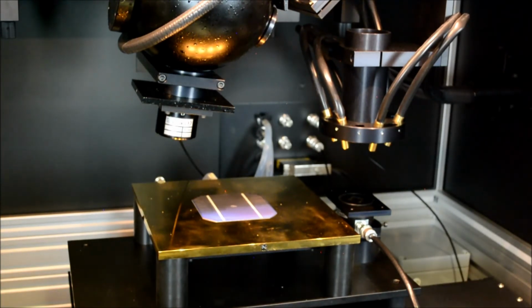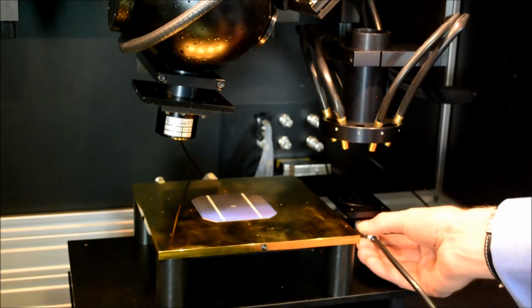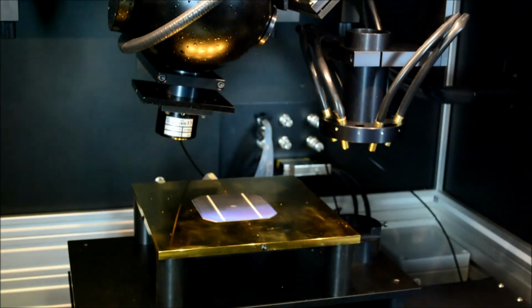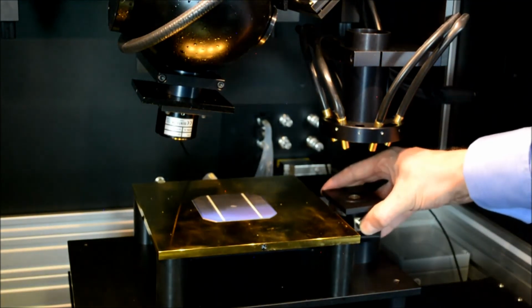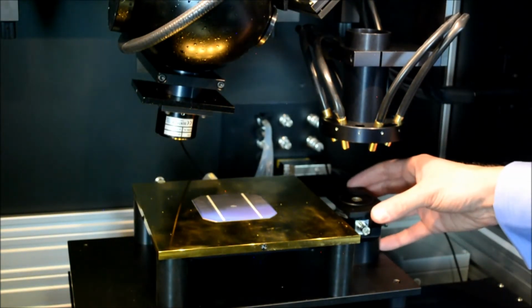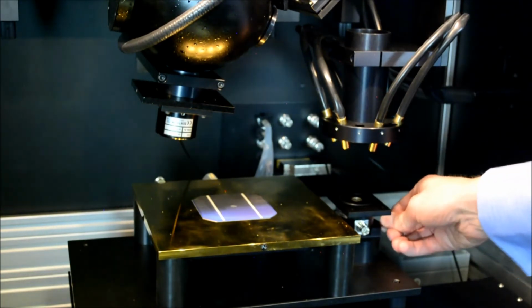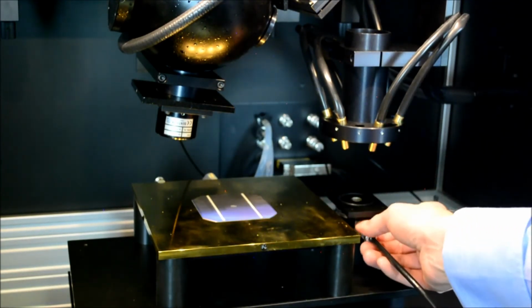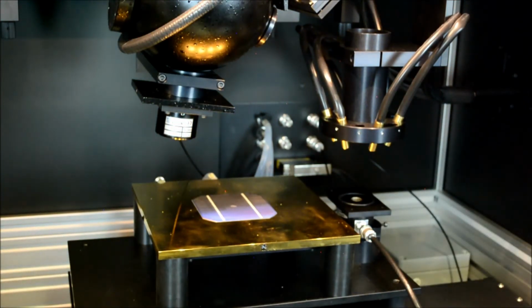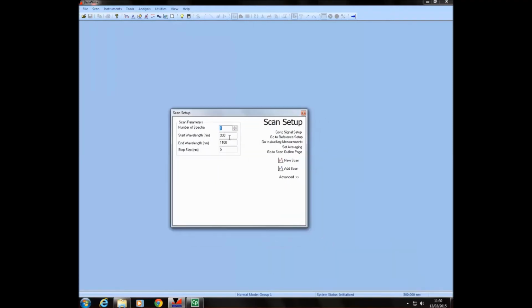So we've calibrated the system presently 300 to 1100 nanometers with the silicon photodiode. So we'll remove that and in its stead place the germanium photodiode to allow us to measure our device up to 1200 nanometers just beyond the band edge. So we'll hold the device in place, connect to the transformer and return to perform a measurement. So now we will calibrate the system with a germanium photodiode over the range 800 nanometers, the minimum wavelength for the germanium diode, to the 1200 nanometers to which we want to measure our device under test. So we select 800 to 1200 nanometers, ensure again that data correction is not selected, and perform our new scan.